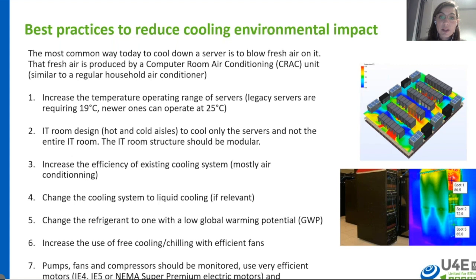The sixth is increasing the use of free cooling or chillers with efficient fans. Last but not least, pumps and compressors should be monitored, using very efficient motors such as IE4, IE5, or NEMA's super premium electric motors, and also incorporating variable frequency or speed controls.